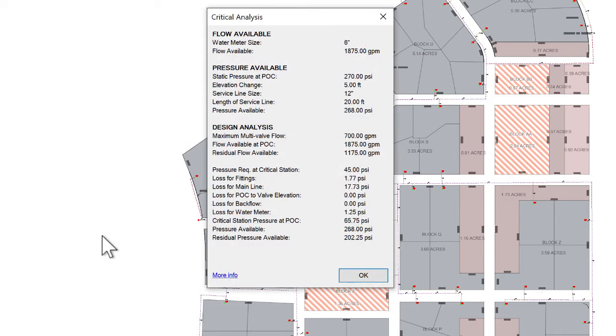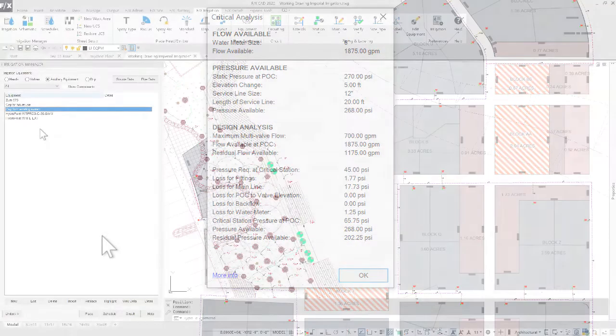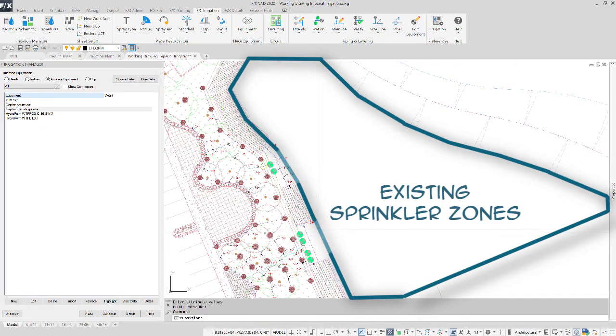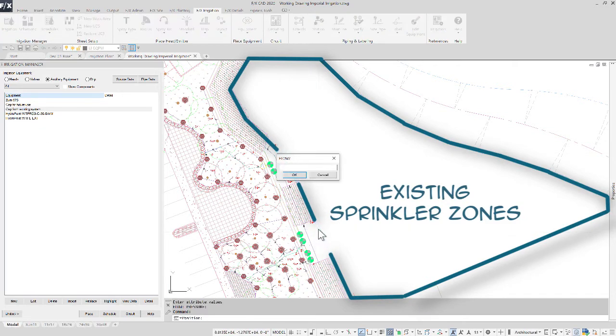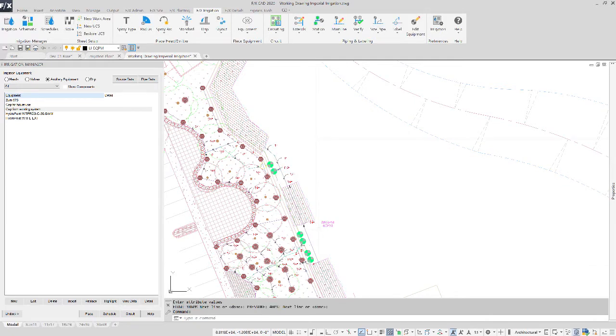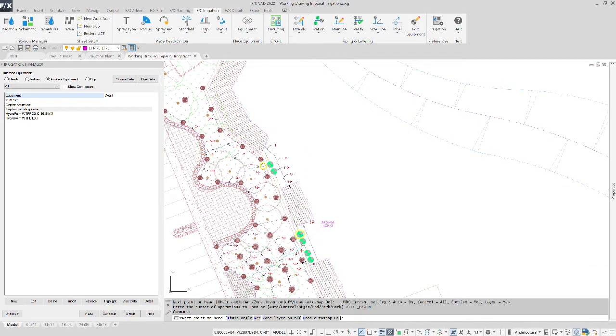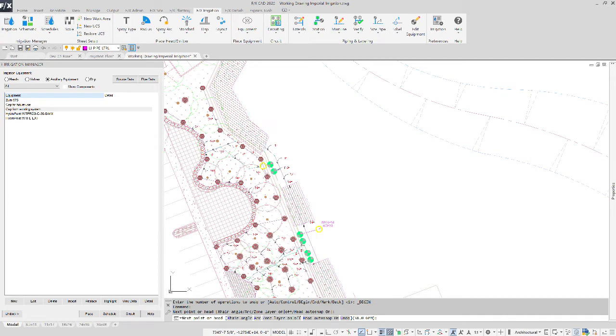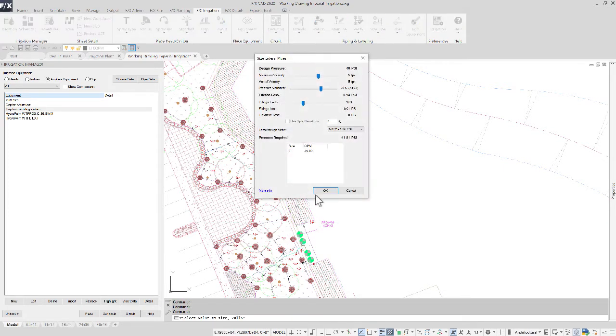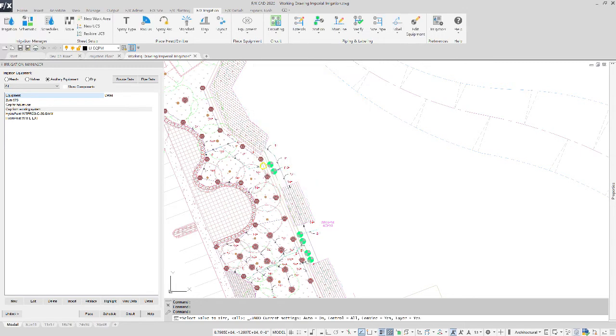When dealing with a site that has existing irrigation that needs accounting for, put a cap directly after the valve and input the required demands of what that cap is representing. Pipe that cap back to the valve with the lateral pipe tool and size the valve accordingly. You now have the accurate flows and pressure required for that valve without needing to place all existing heads for that zone.